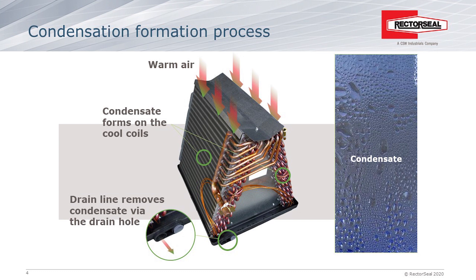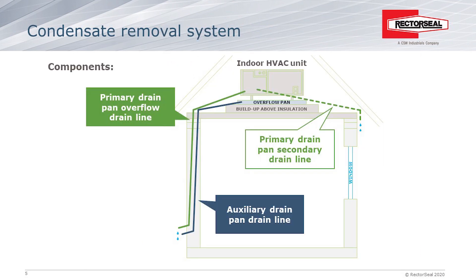At the bottom of the evaporator coil is a drain pan that collects the condensate water. These drain pans typically have two outlets: a primary drain outlet that carries condensation away, usually outside the home or office, and a secondary outlet in case the primary gets clogged. Float switches mount onto the secondary outlet so that if the primary drain line clogs, the water fills up, raises the float, and shuts the unit off to prevent the drain pan from overflowing.